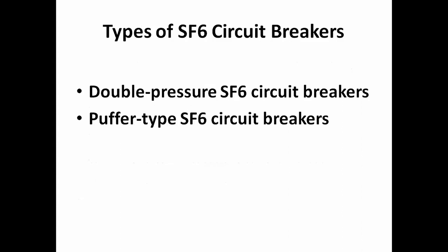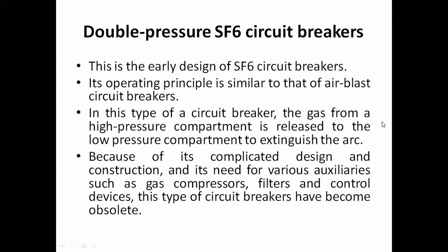So if we talk about the types of SF6 circuit breaker, there are two types. Number one is called the double pressure SF6 circuit breaker, and number two is called the puffer type SF6 circuit breaker. Mind that the double pressure SF6 circuit breaker cannot be used nowadays because it has certain disadvantages. We are not using the double pressure SF6 circuit breaker recently. Nowadays we are basically using the puffer type SF6 circuit breaker. Now let us see what the disadvantages of this double pressure circuit breaker are. See, the double pressure SF6 circuit breaker is an early design of the SF6 circuit breaker.